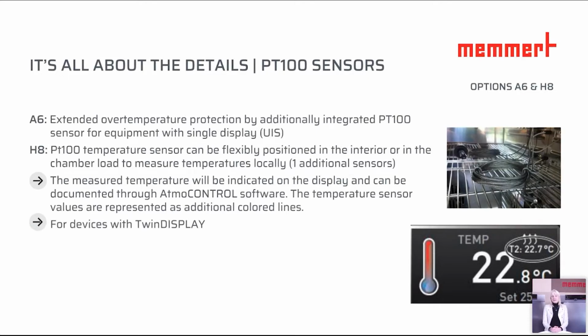For surveillance purposes, we have the possibility to place additional flexible PT100 sensors in order to measure directly at the surface of the samples. In our standard units, for some single units we have one sensor included that is put in the best position for controlling the temperature in the interior. And additionally, for our twin class models, which already have two sensors for temperature measure and over temperature protection, we have this flexible sensor, which is also a PT100 sensor, which we can see here on the picture.